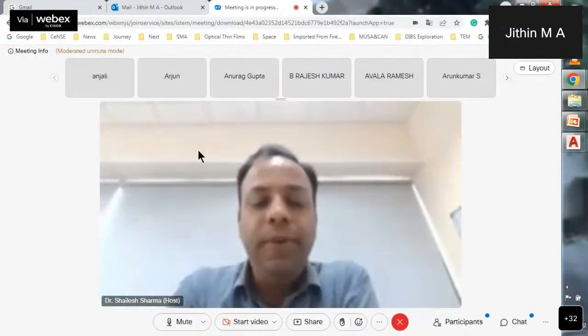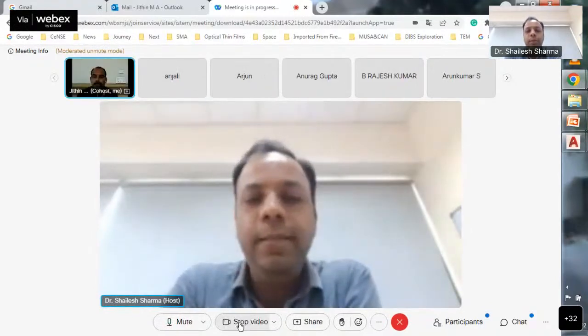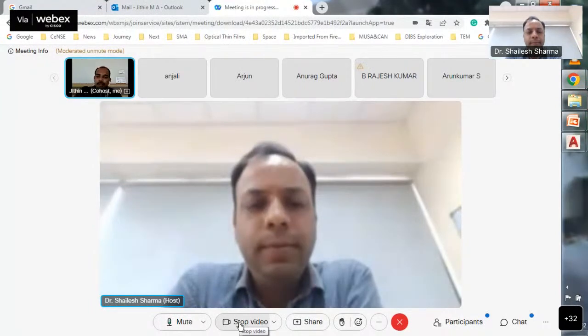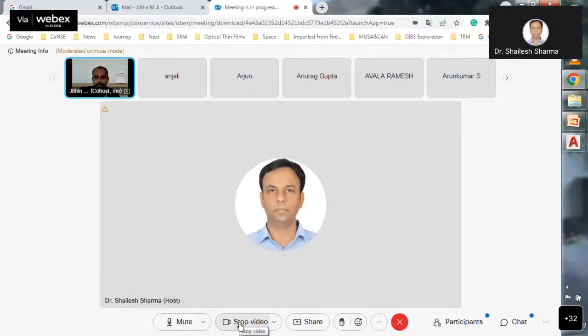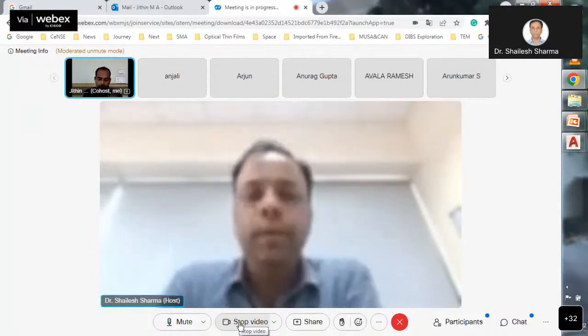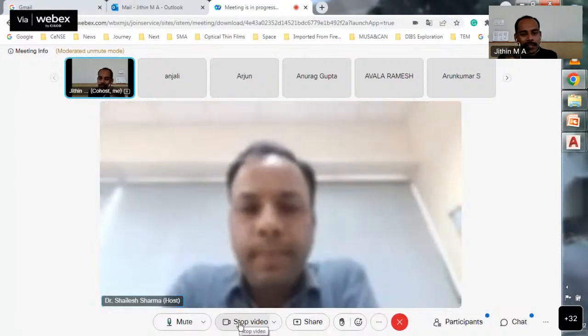So Jithin, one question from my side. You said about RGA, residual gas analyzers. Is this RGA able to detect almost each and every gas, or is it specific to certain gases? The atomic mass unit range is from 1 to 200 AMU. So in that range, any gas we can measure. Whatever RGA we have in the lab, it is 1 to 200 AMU. Almost all the gases which we use regularly will come between 1 and 65 AMU.